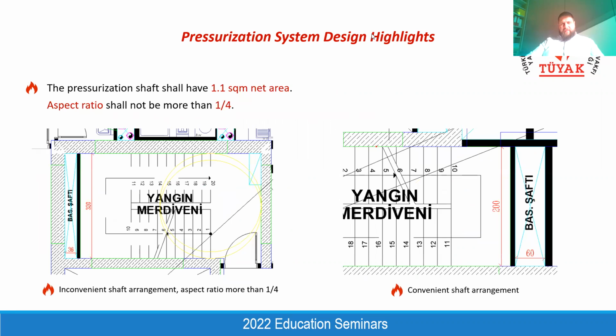This is really important, because a wrong design can cause problems during the handover stage. If you have a pressurization shaft, the net area shall be not less than 1.1 square meter. It comes from the performance and functional test of the pressurization system conducted on site. This is not a written rule, but our inspections show that the shaft area shall be not less than 1.1 square meter. Otherwise, the velocity of the air increases, causing higher pressure loss, and the pressurization system will not work as required. We cannot see the required pressure difference between the staircases and the lobby. That's why the area should be not less than 1.1 square meter.